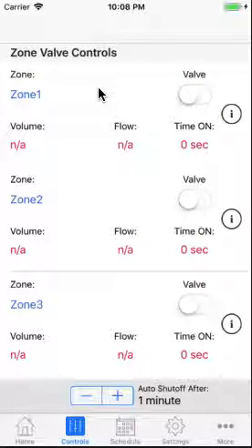After the first activation, the valve will respond immediately when activated unless you have changed hardware and press the Reconfig button on the Flow Meters tab of the app. This is only done when you have removed or added flow meters to your irrigation system, in which case the system will again need to check if flow meters are associated with the activated valve.